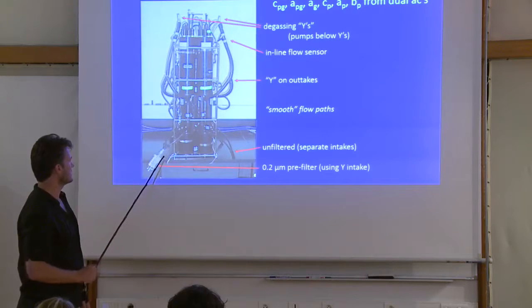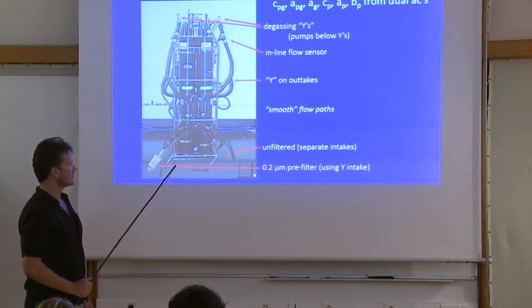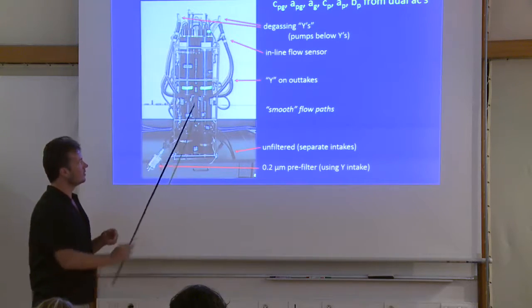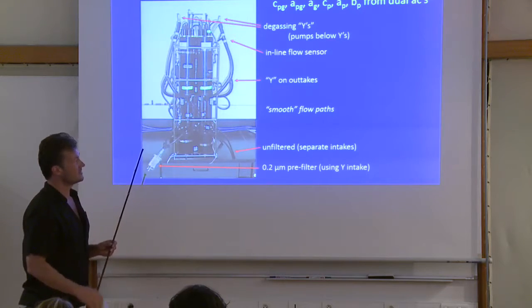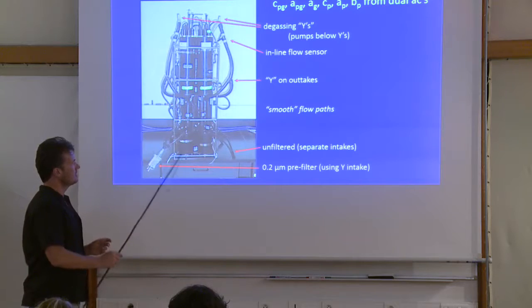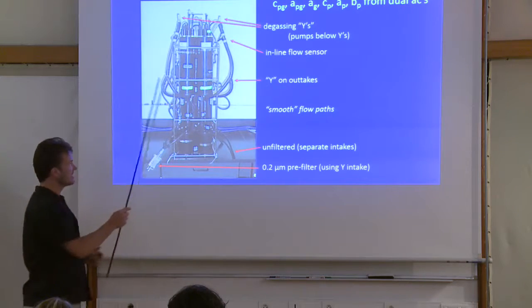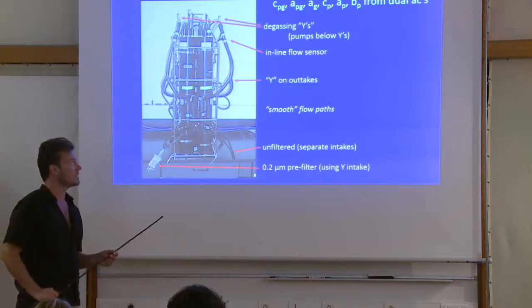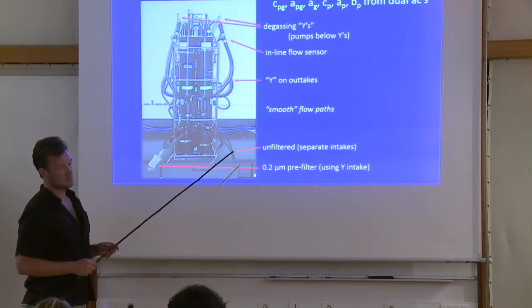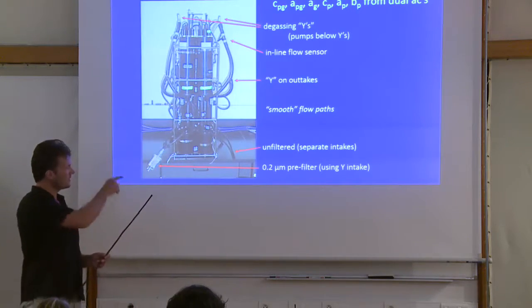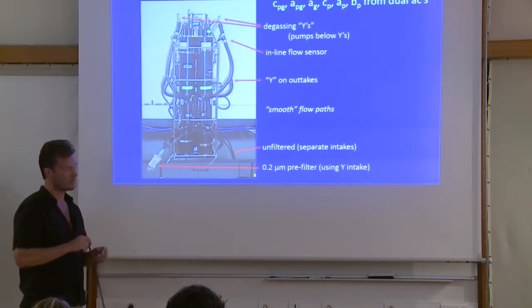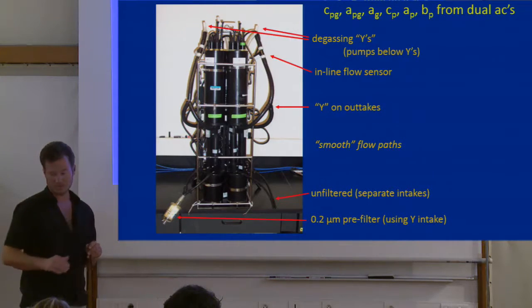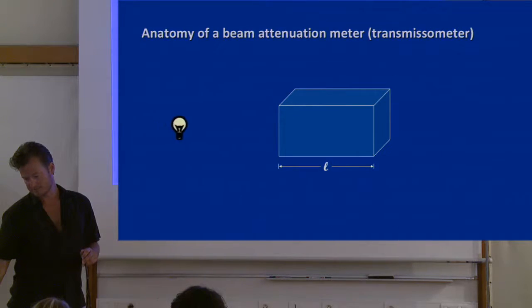So even with one AC device, you can have a switcher here that goes between the filter and totals. And so you can do one profile filter and then do another profile total. And you can do all of that with a single AC device. And there's the added benefit, as Emmanuel was saying yesterday, that the calibration, when you do that subtraction with the same device, cancels. So it's actually probably the most accurate measurement you could possibly make, particulate attenuation and particulate absorption, with that switching technique. And he's done that on the Tara with great success, and the instrument's been drifting the entire time, and he still gets particulate absorption spectra with, frankly, incredible signal to noise.